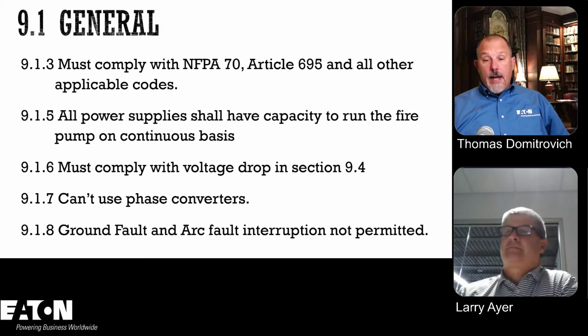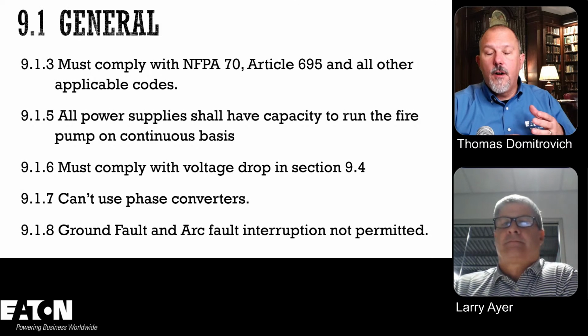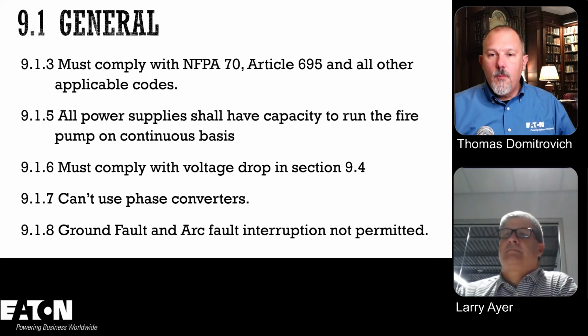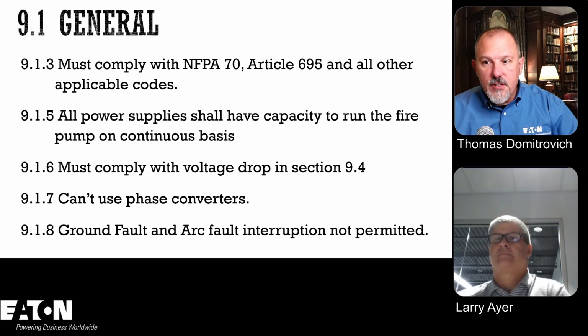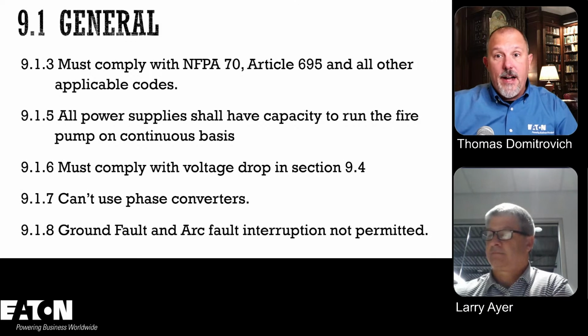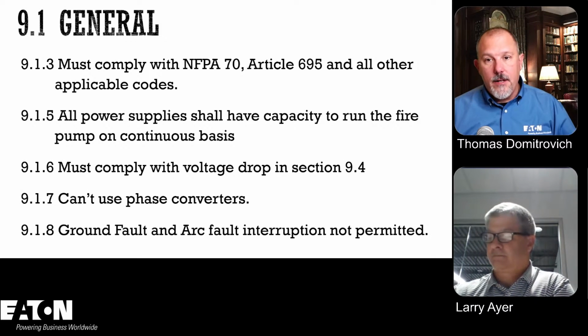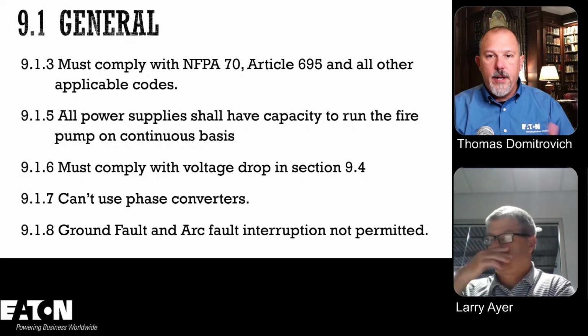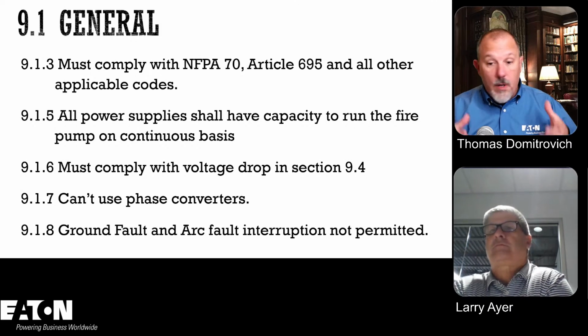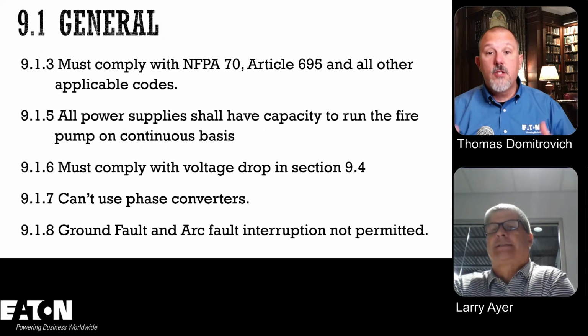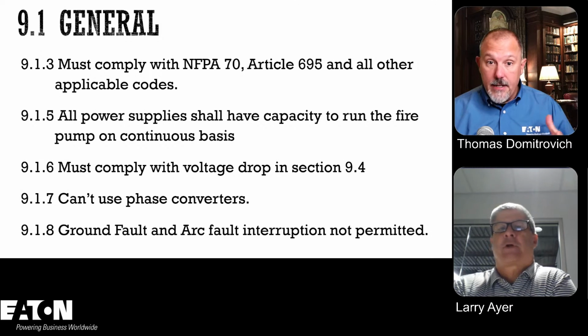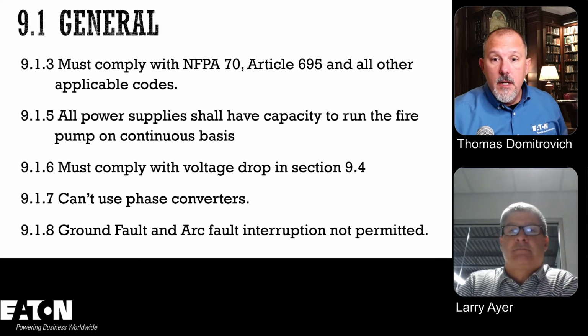Yeah, and I think one of our first slides said we're not really worried about personnel safety. I mean, we're worried about personnel safety indirectly because we're putting out a fire to save the structure, to let you get out and let the sprinklers work and all this other good stuff. But we're not necessarily worried about creating that shock hazard or creating an arc flash event and things of that nature. We just want this puppy to run, and we want it to run until it fails because you need it. Yes. Yep. Can't use phase converters as well.